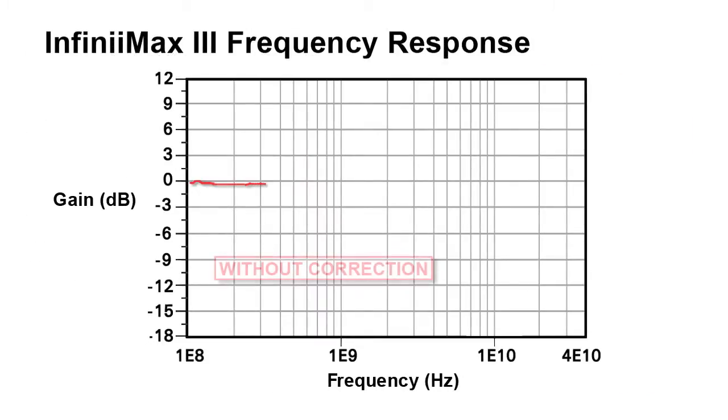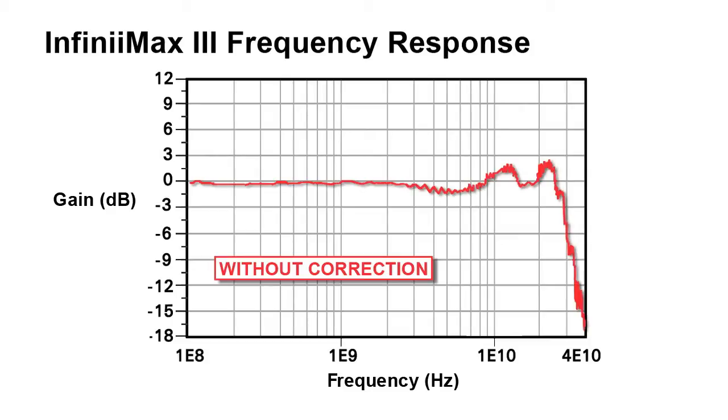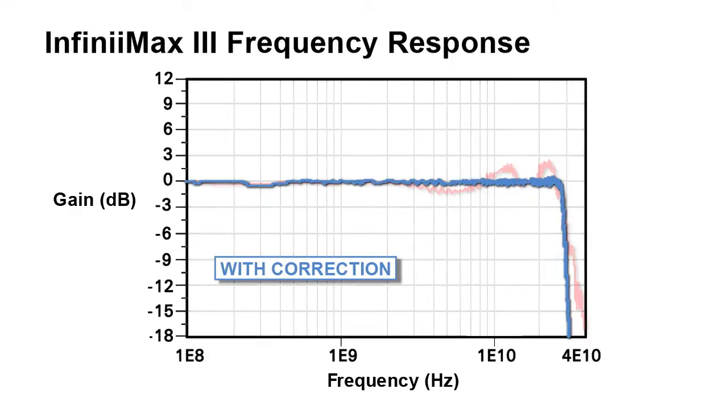Each individual InfiniiMax III+ probe amp contains the unique S-parameter of each probe and is used with the S-parameter of the various probe heads to further flatten the probe's frequency response. This results in more accurate probe corrections for more accurate measurements.